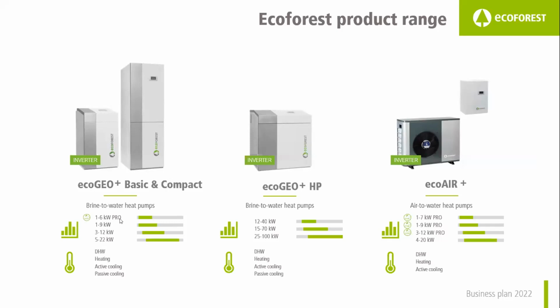When you see the surname Pro, it's because we are using R290, or propane, as refrigerant. With this unit, we can provide domestic water heating, active cooling, and passive cooling. The only difference between this range and the other is the elements included. In the Basic and Compact, we include all the elements of the installation inside, like expansion vessels, brine production, and circulation pumps.